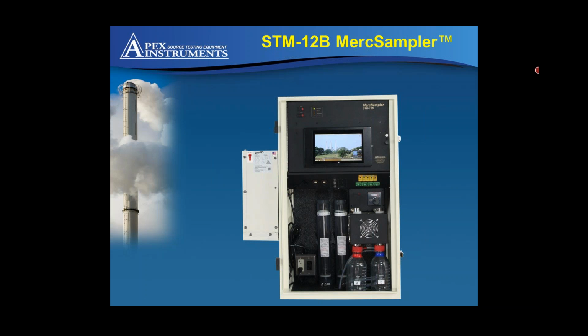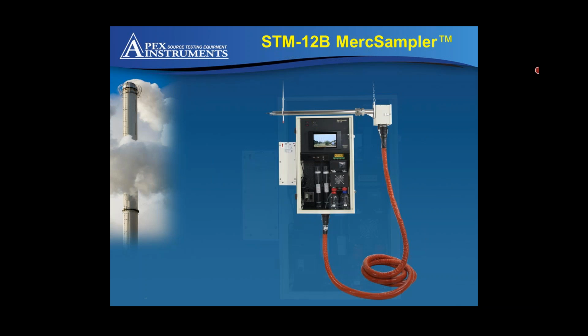Some of our other competitors have systems with peristaltic pumps which pump this moisture away. We've deliberately gone with this setup for several reasons. One is that we might be able to petition the EPA to do that gravimetric Method 4, which would save you another step. It's already there. Why not use that information? And secondly, we've got a closed system. When you are pumping away that moisture with a peristaltic pump, you are losing some of your sample volume, up to 4 or 5%. And that can definitely bias some of your results, especially if you're running very close to limits and things like that. So you want to have a closed system to make sure that the integrity of the data coming out is as good as you can get.